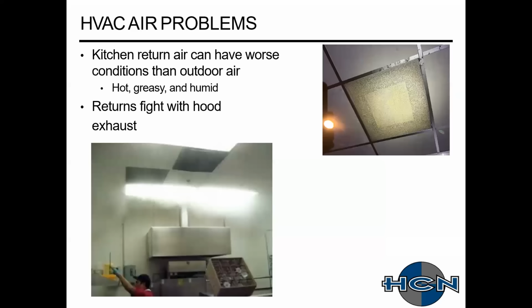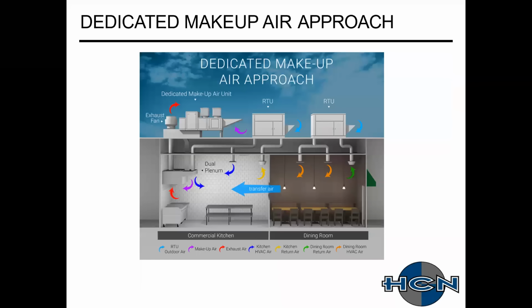So usually the problem you have with any of these kinds of designs is your kitchen return air is pretty bad, especially if we're diffusing a lot of that nasty air that's supposed to be captured by the hood and it's getting thrown out into space. So with these returns, a lot of these could be a pretty hefty size.